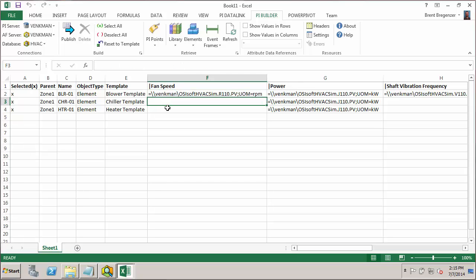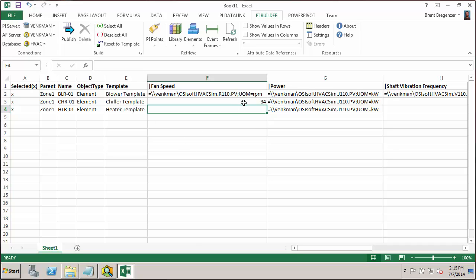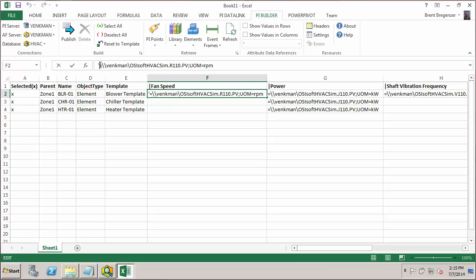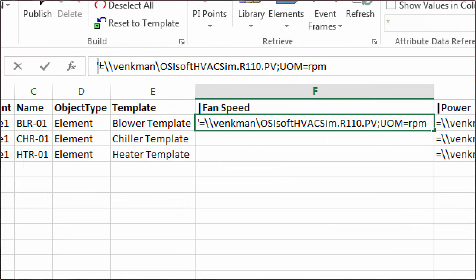So if I just put something like 34 here, it would go in and it would plug in 34 as the attribute value. But since we want to actually change the configuration string by adding a new tag for the PI point data reference, we need to have an equal sign beforehand. The other thing you'll notice is that because Excel will interpret a leading equal sign as the beginning of a formula, an Excel formula, we need to have this single quotation mark in front as well. And that's just going to tell Excel to leave this text alone and not try to interpret it as an Excel formula.